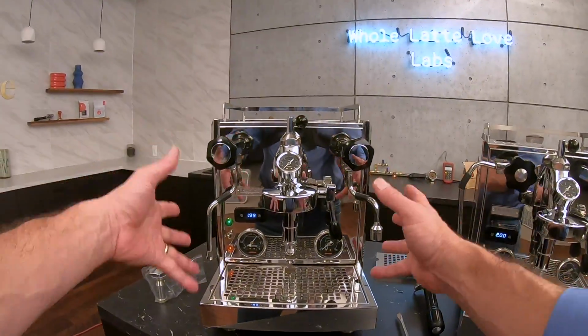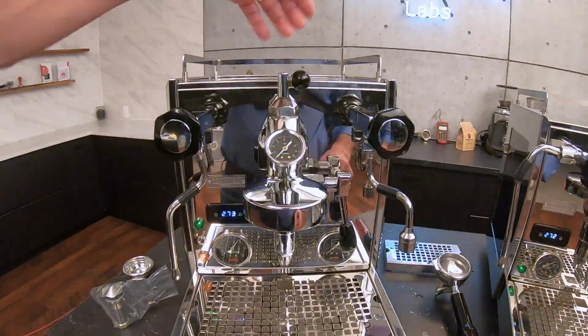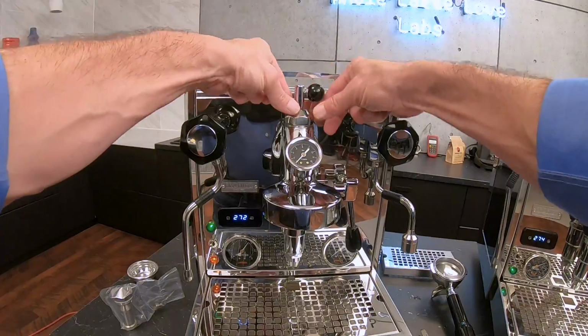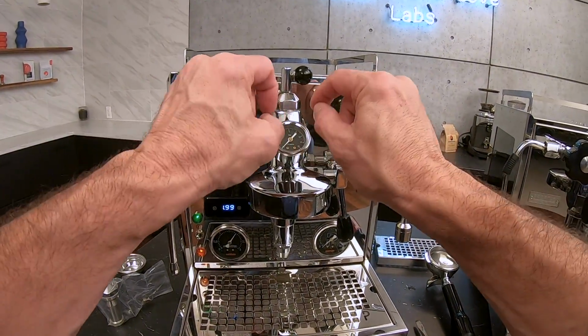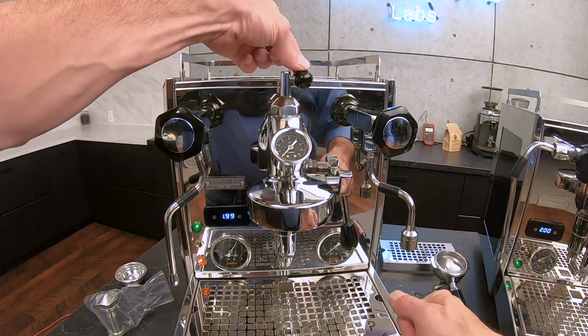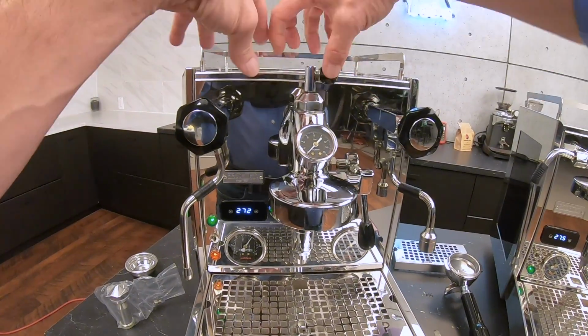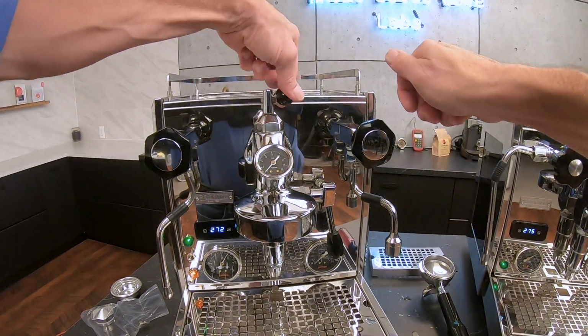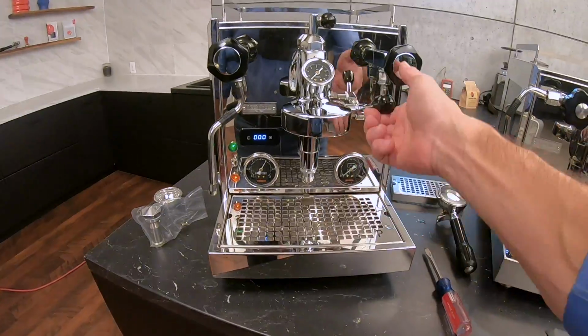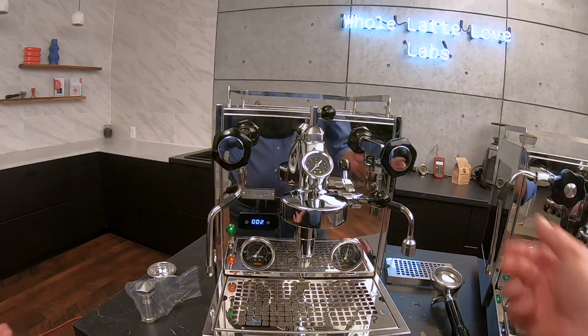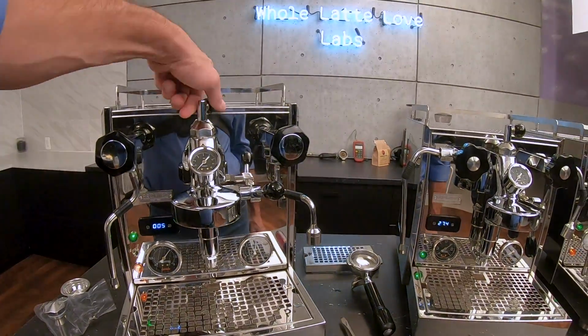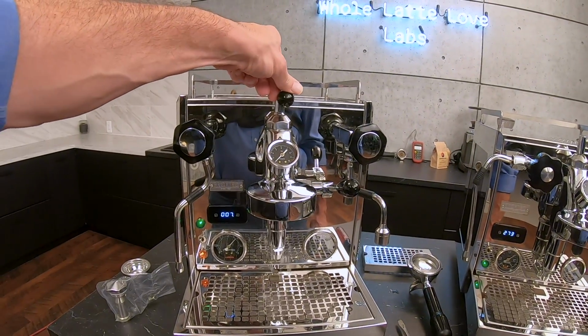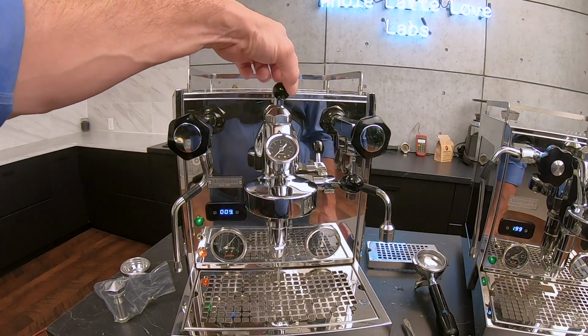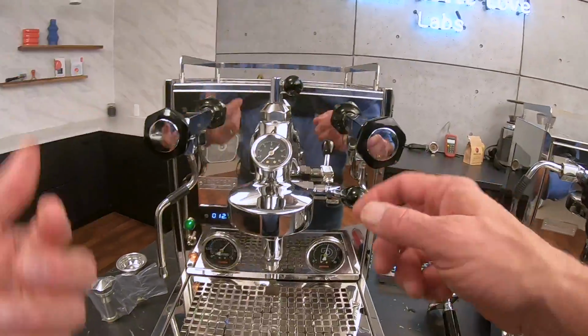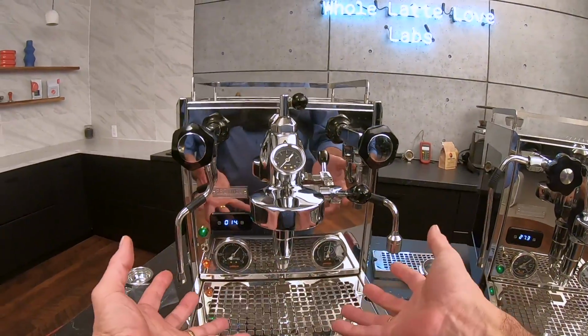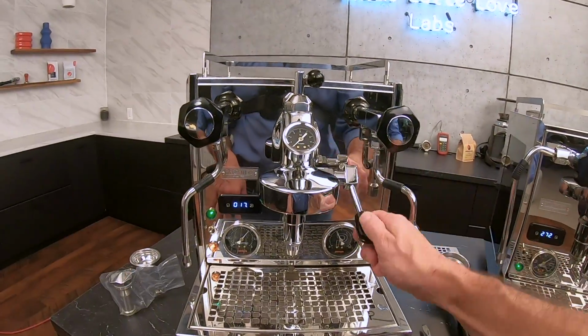So let's take a look at the device and checking your calibration. This is the flow control device right here, and you also get the group pressure gauge. To check the calibration, turn it all the way clockwise to fully close flow, turn the pump on, and you should get no flow when you're fully clockwise. Then as you open it up by turning counterclockwise, you get flow, and it's about one full turn. So if you're fully clockwise and you're getting some flow, you're a little bit out of calibration. I'll show you how to take care of that.